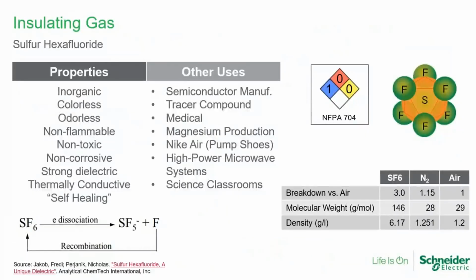So let's talk a little bit about those insulating materials. Most of the time when we're talking about gas insulated switchgear today, we're talking about SF6 or sulfur hexafluoride. It's a gas that's been used for a long time in the electrical industry as a dielectric material. It's inorganic, colorless, odorless, non-flammable, non-toxic, non-corrosive. Obviously a very strong dielectric. It's thermally conductive, which means it's going to transfer heat to allow for heat dissipation of the switchgear fairly easily. And it has a self-healing property in the sense that when an arc happens inside of SF6, it does break down the molecule, but the molecule naturally wants to recombine and come back together.